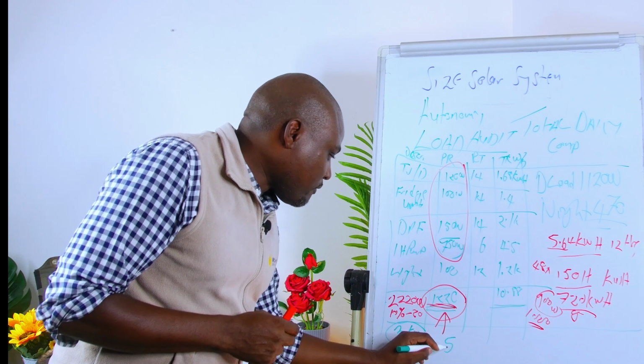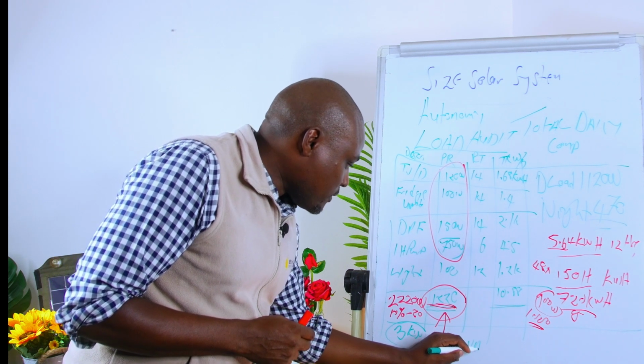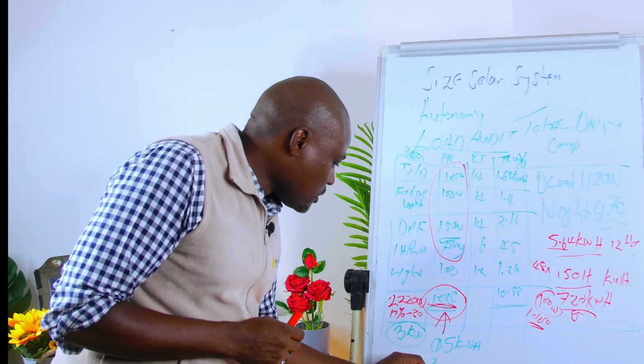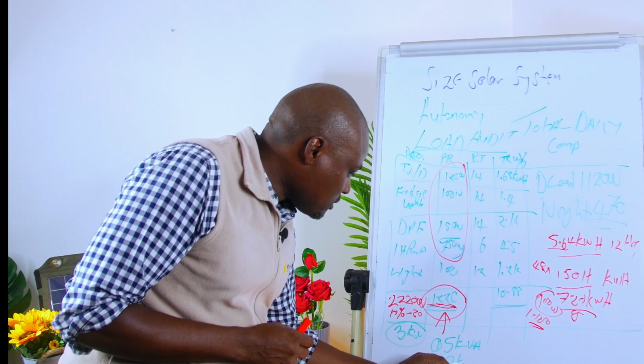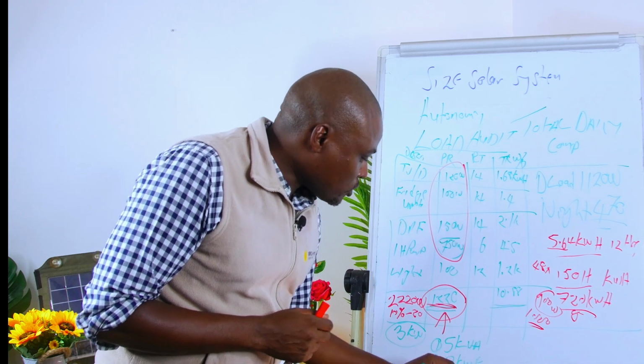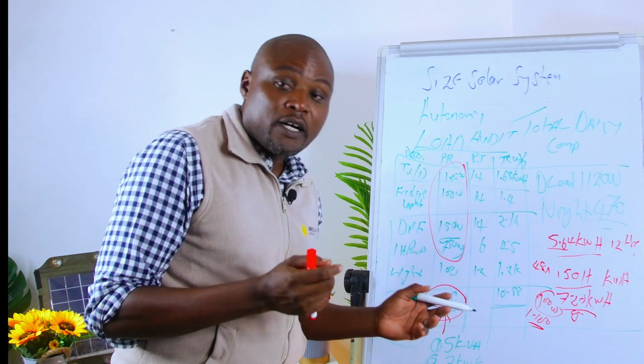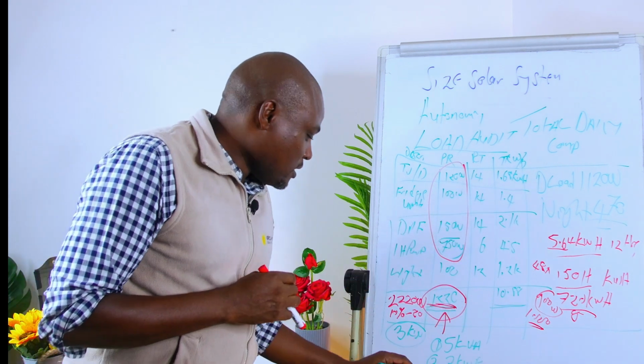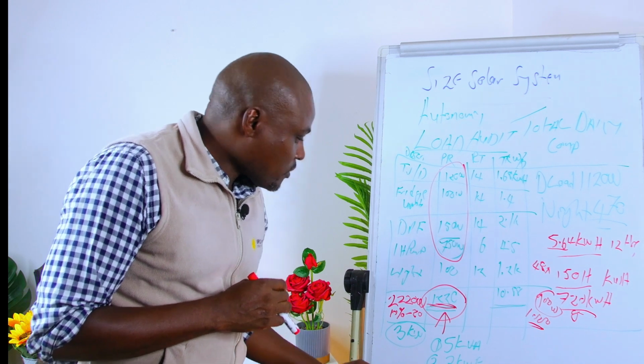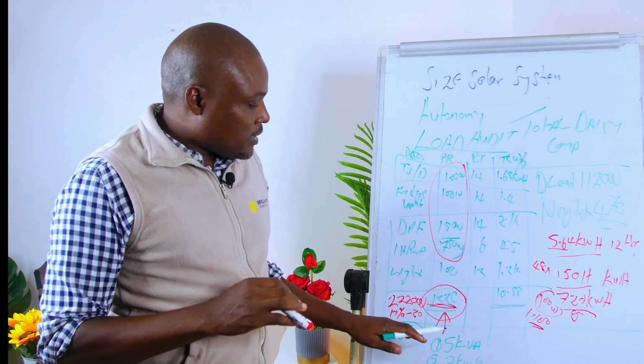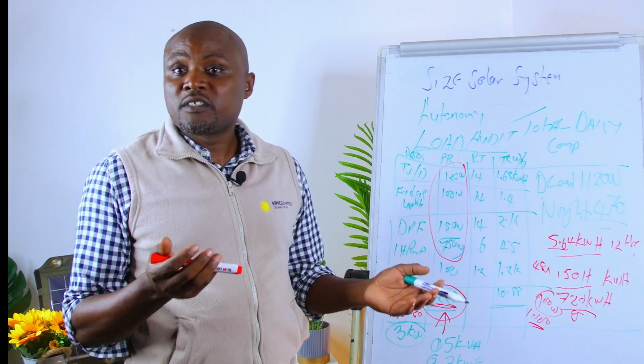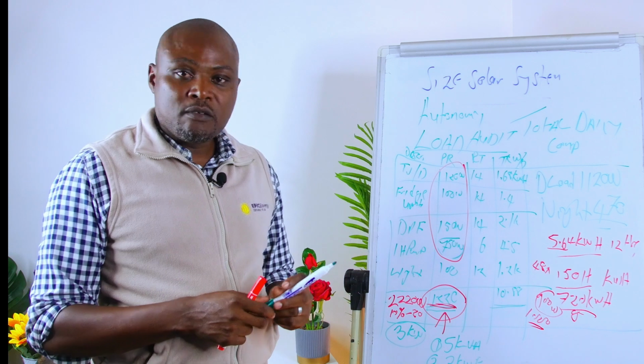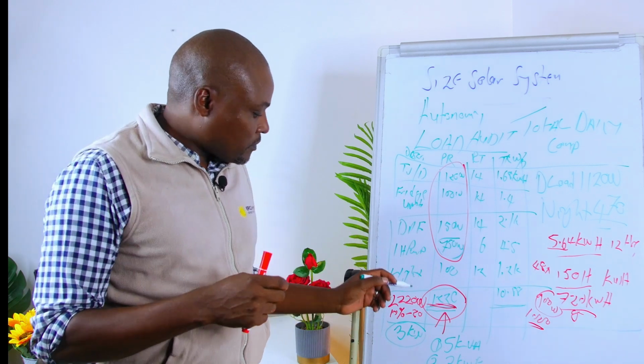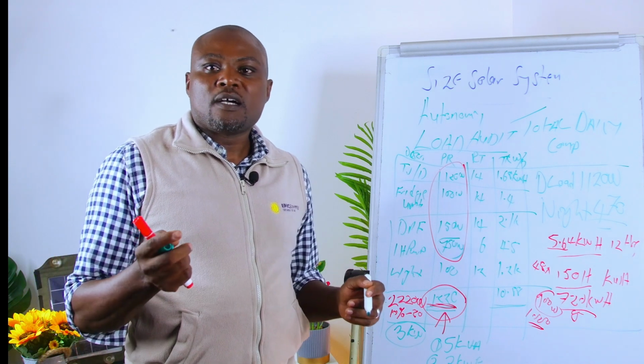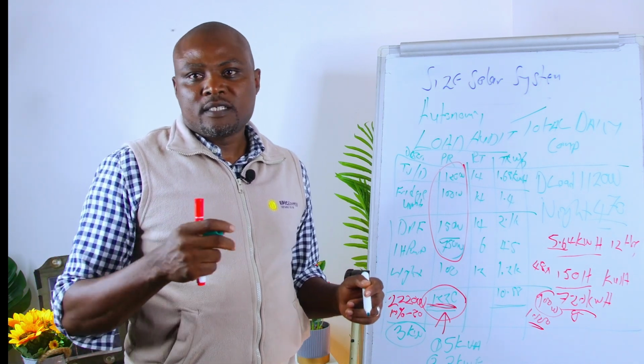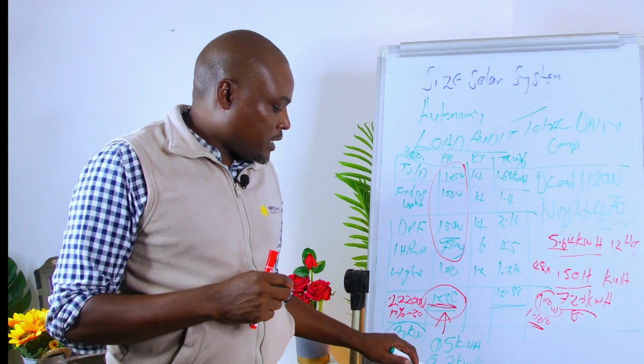So in this case, we'll offer the client a 5 kVA inverter. Then we'll offer them, number 2, maybe a 3 kilowatt peak solar array. Most probably we are talking of 550 by 6. Then the battery bank is a 150. So because it's a hybrid inverter, it comes with an inbuilt MPPT which can accommodate maybe 450 high voltage solar array where you just connect them in series, or it can be a low voltage with high amperage, which is your current, about maybe 60 amps or so, which is able to accommodate the setup.